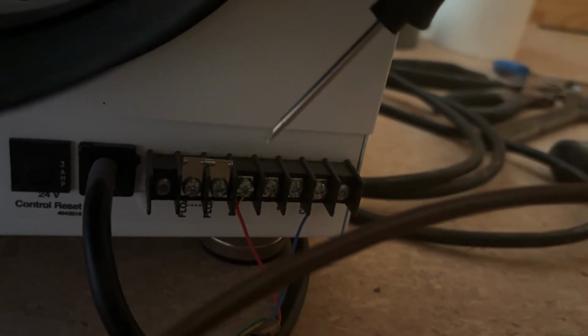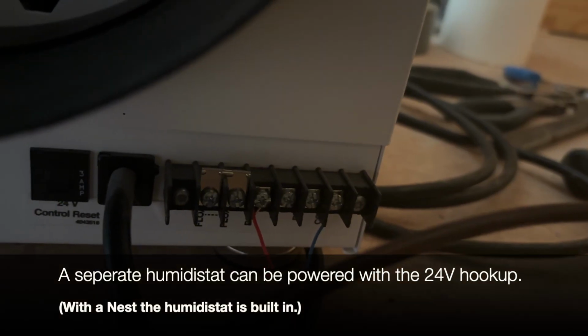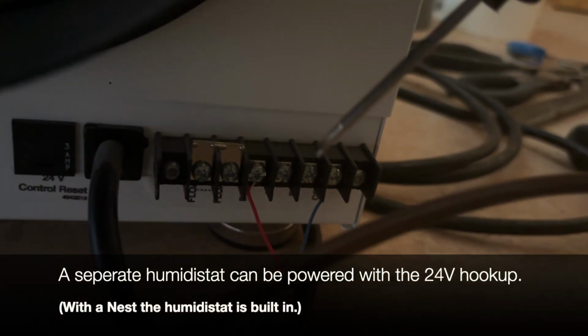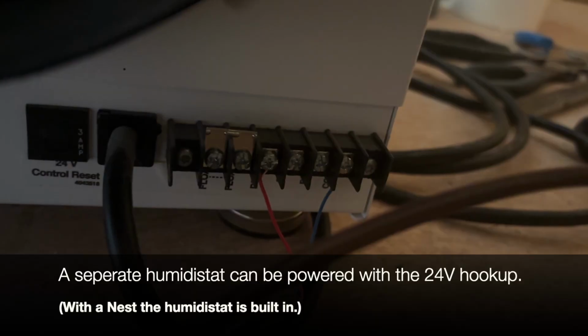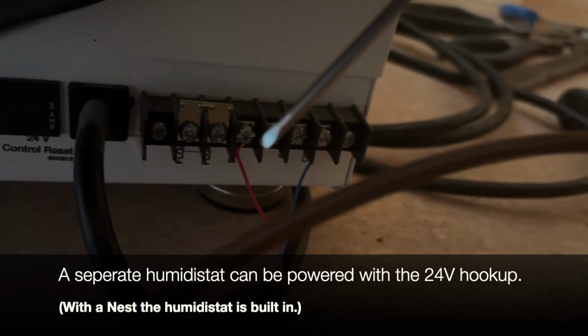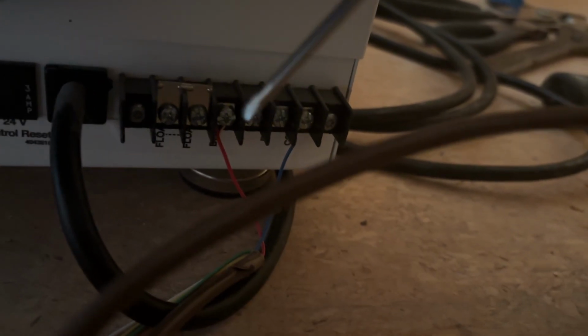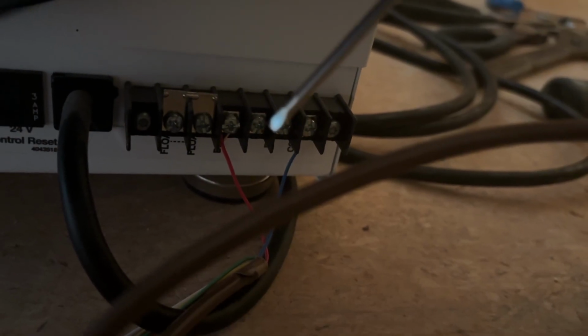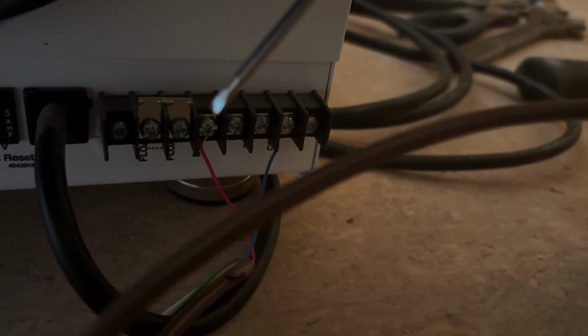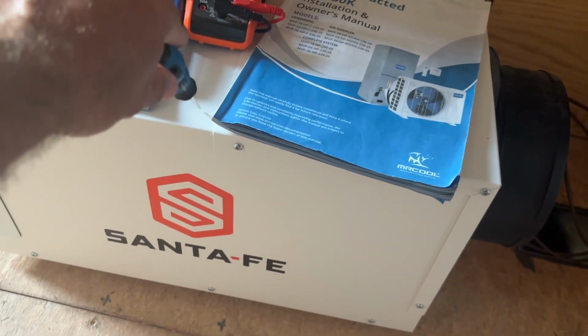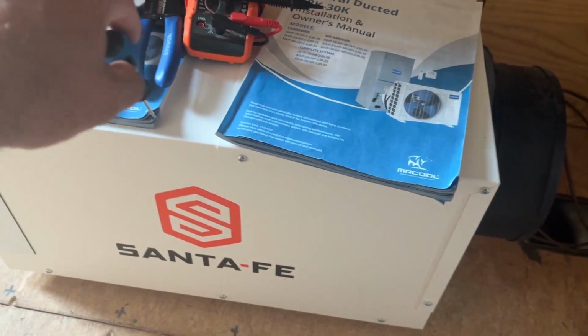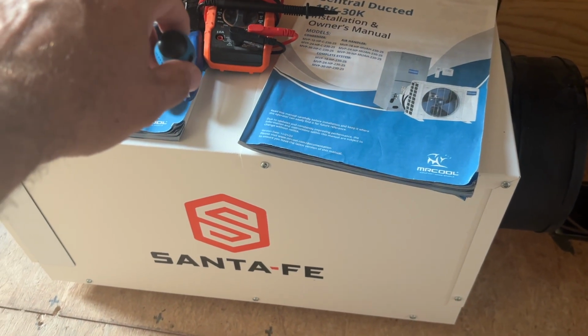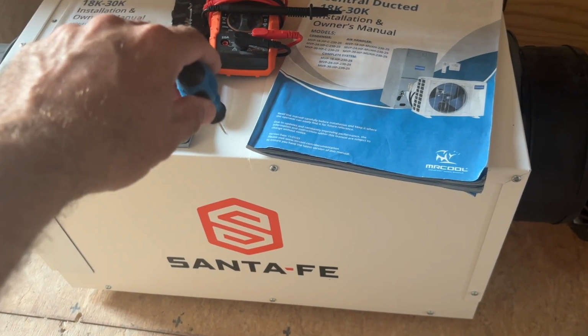You have other options. You can hook other equipment in here. You also have a 24-volt transformer in here too, so you can power accessory equipment off of your dehumidifier if you need to. But that's the wiring there. So just 2 coming off this, going right back to the thermostat, which allows the thermostat to control this. Once the humidity goes above whatever your set point is, I have mine set at 50%, it'll kick this thing on.